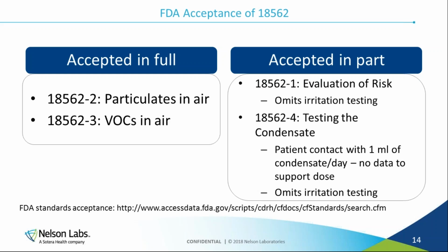And then for part 4, where it talks about testing the condensate, there's a lot of language about this 1 ml of condensate per day dose to a patient. However, there's no supporting literature that was identified for that specific 1 milliliter per day dose. So the FDA doesn't support addressing it that way. As I talk about part 4 testing later in this presentation, I'll give specifics about the testing that we have worked out with the FDA and let you know what they'd like to see.